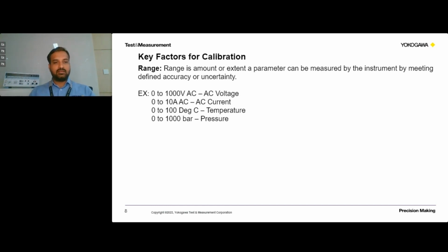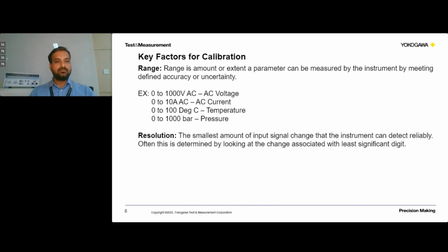For example, for electrical parameters such as voltage and current, it will be defined in terms of 0 to 1000 volts, or 0 to 10, 0 to 100 degrees centigrade. And if it is for pressure, it will be defined like 0 to 10 bar, 100 bar, 1000 bar, like this. However, when it comes to actual testing, the minimum value of the input will be defined in terms of a percentage of the full range, like 1% of the defined range. It will not exactly start from zero.